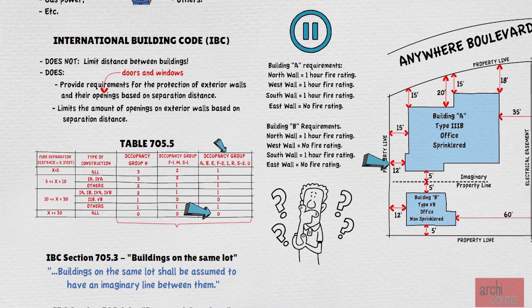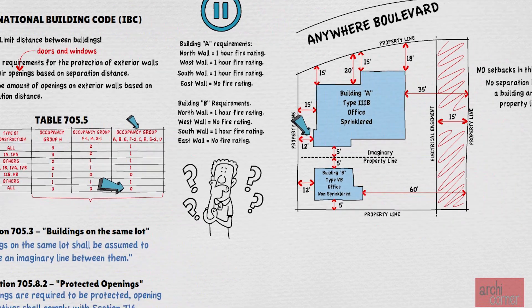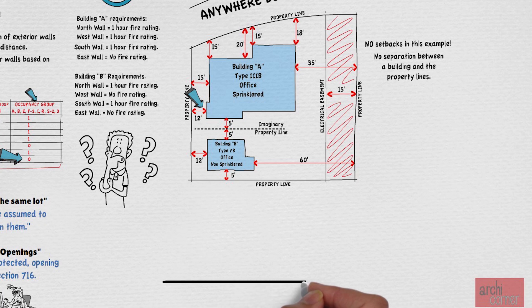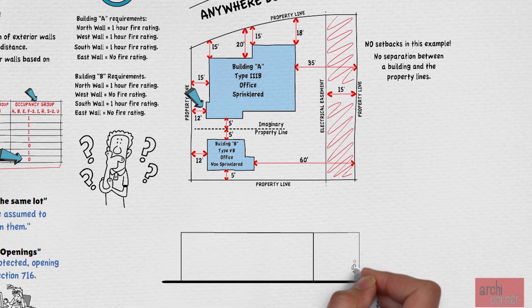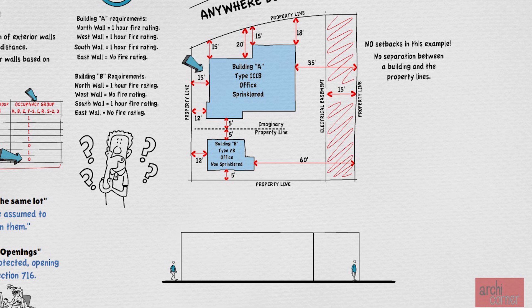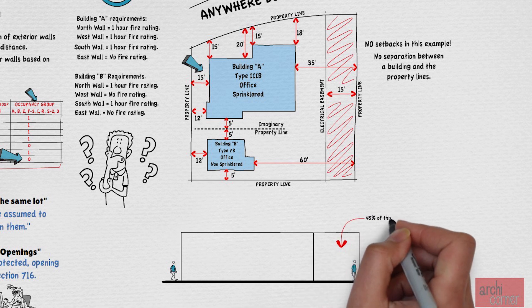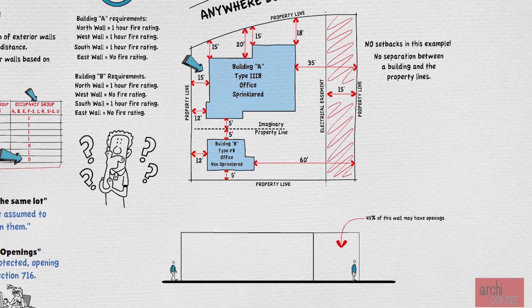Back to where we left off: we determined that this wall can have openings that take up to 45% of the wall. This means we must think of this wall in an elevation view, so let's draw an elevation of the exterior wall. I am going to draw both of these walls — the wall that is 12 feet away from the property line and also the wall that is 15 feet away from the property line. The section that is 12 feet away from the property line may have up to 45% of the wall provided with openings. By the way, in case you're wondering what we mean by openings — we're talking about doors and windows. Therefore, we may have a large window as long as the area of the window does not exceed 45% of the wall area.